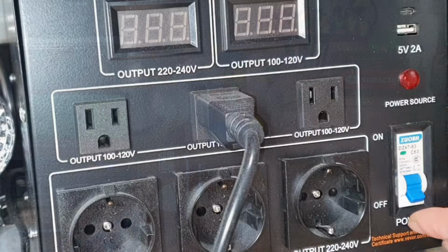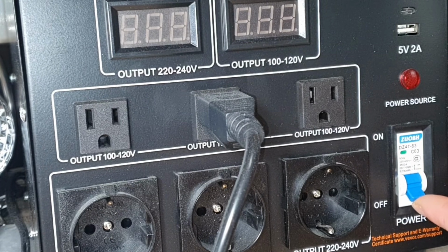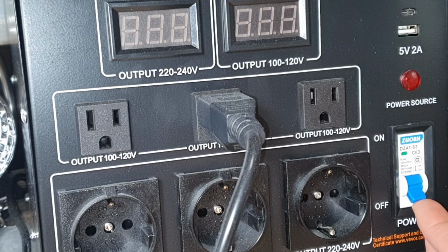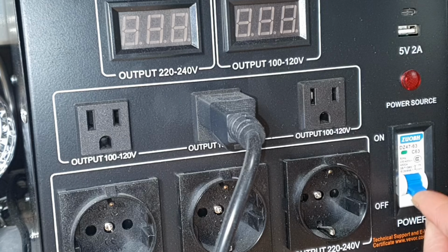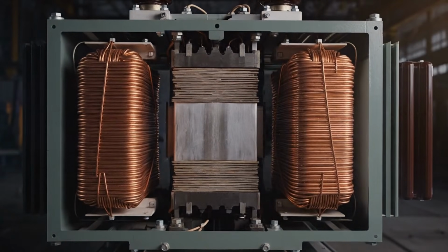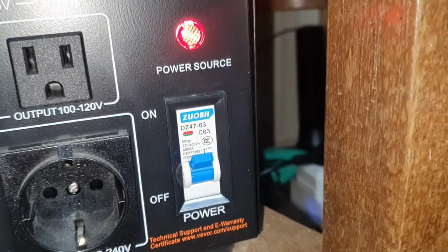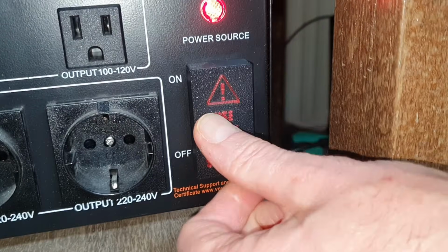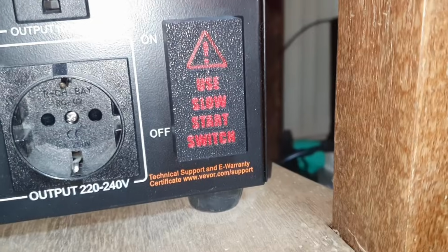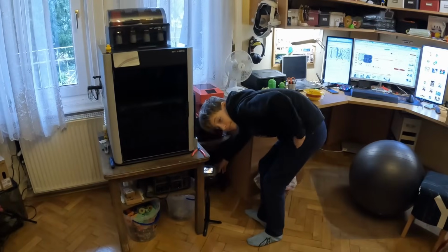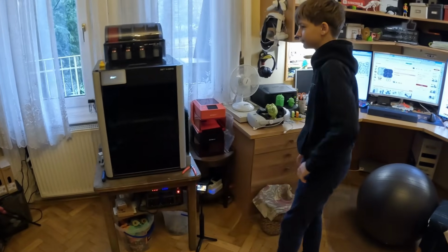But there's a risk. That giant blue breaker on the transformer is just too inviting. If someone turns it off and then flips it back on while our soft start module is already active, we completely bypass the protection. We would be right back to square one with a massive inrush spike and the blackout lottery. To stop this from happening, I switched the transformer to the on position and printed this cute informative cover. It physically blocks the breaker to prevent me, Levi, or anyone else from accidentally going around the slow start module.